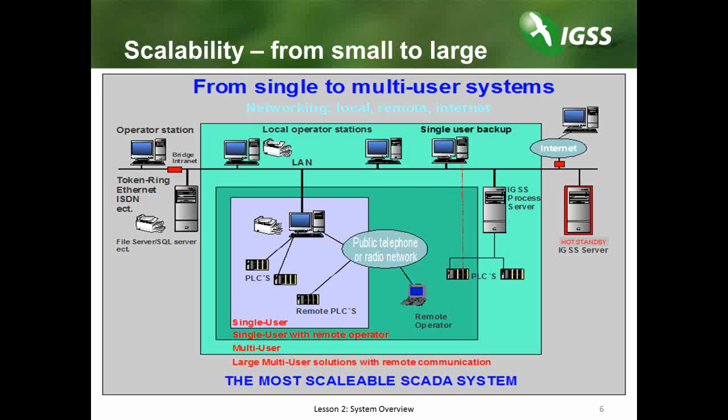Scalability from small to large. I'd like to explain a little bit about the scalability in IGSS, going from small scale to large scale operations. Looking at the slide, we can see how we start small and grow larger, adding more operators, servers, and connection options. In the middle we have a single user system — the smallest system available in the IGSS software package — with a server and a monitoring process located on one and the same PC. The PLCs are connected to the one PC, which is both server and monitoring station. We can add to the single user system and connect a remote operator, perhaps connecting through a public telephone or radio network.